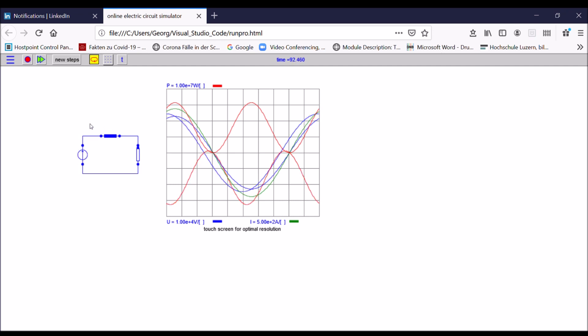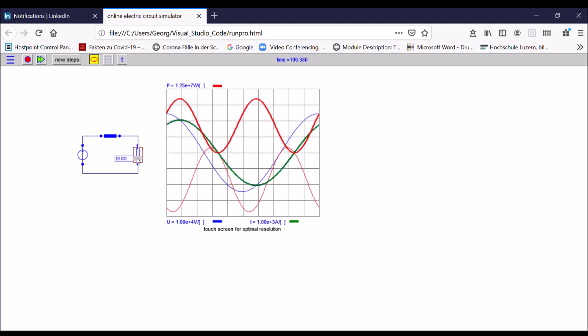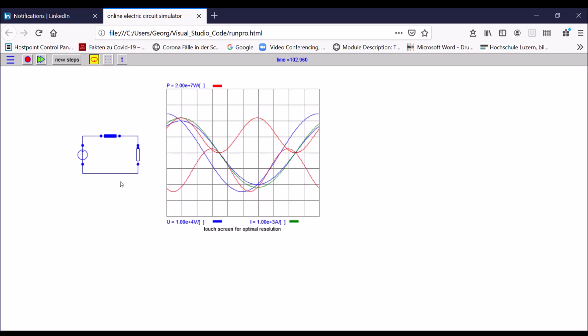The reason is that this series inductance starts to play a role now. As I continue to increase my load, you can see that the voltage of the generator starts to decrease further. This is exactly the moment where the automatic voltage control of the generator starts to kick in and increase the voltage, so that the output voltage at the terminals stays equal to the nominal voltage. The generator voltage control increases the magnetic field of the rotor by increasing the DC current in the rotor.